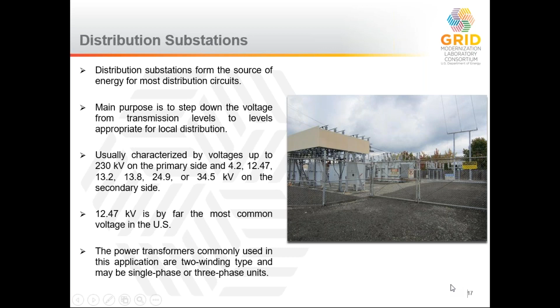Next slide, please. Within the substation, the single most important piece of equipment are the step-down transformers. These are large pieces of equipment that are designed to operate for 30 plus years. I've seen units in operation for over 50 years. Their primary function is to take the incoming power from the sub-transmission or transmission system, step it down to the lower voltage, and supply that out to the distribution circuits that head out into the system. The number one threat to these devices is heat. As you load them higher or put large spikes of power through them, that heating will degrade the internal electrical windings inside, and that'll reduce their lifetime.